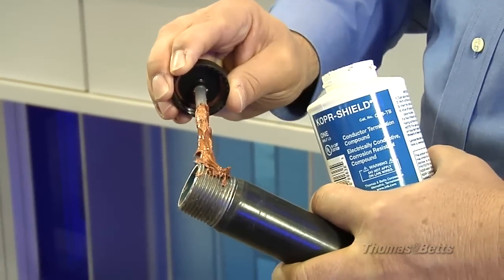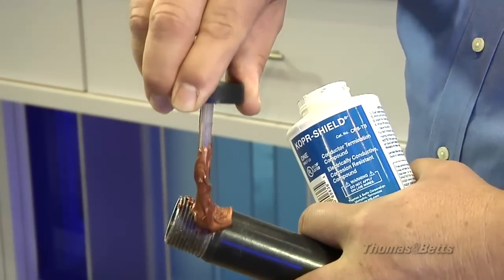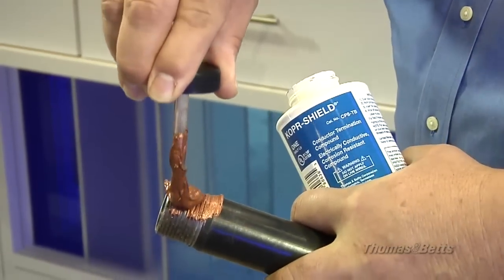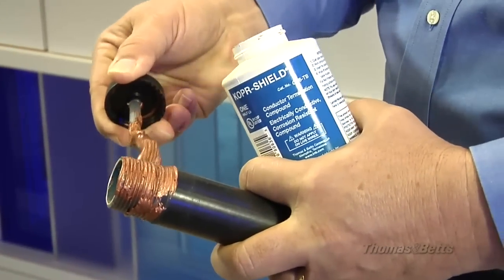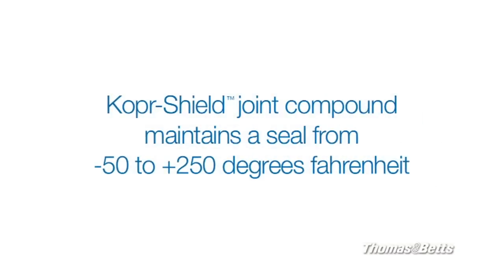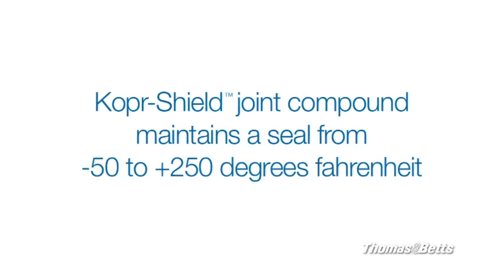Here are two ways that T&B can add value. Kopr-Shield Joint Compound can be used to seal field-cut threads while securing the bond for a path to ground. Its unique blend of pure copper plus corrosion inhibitors brushes on easily and maintains the seal at temperatures ranging from minus 50 to plus 250 degrees Fahrenheit.